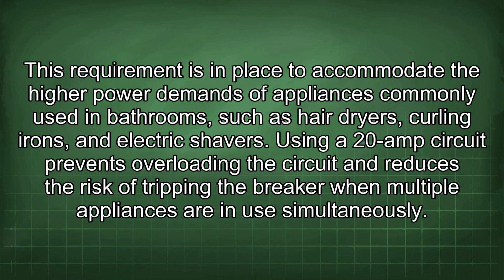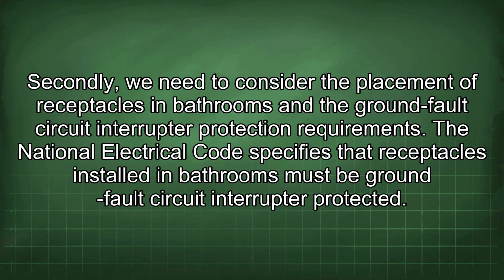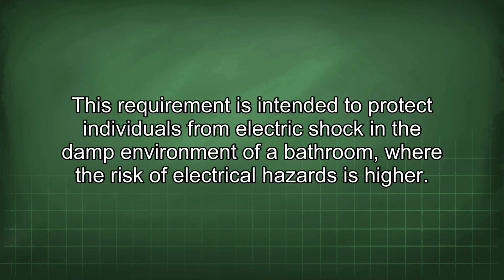are in use simultaneously. Secondly, we need to consider the placement of receptacles in bathrooms and the ground fault circuit interrupter protection requirements. The National Electrical Code specifies that receptacles installed in bathrooms must be ground fault circuit interrupter protected. This requirement is intended to protect individuals from electric shock in the damp environment of a bathroom, where the risk of electrical hazards is higher.